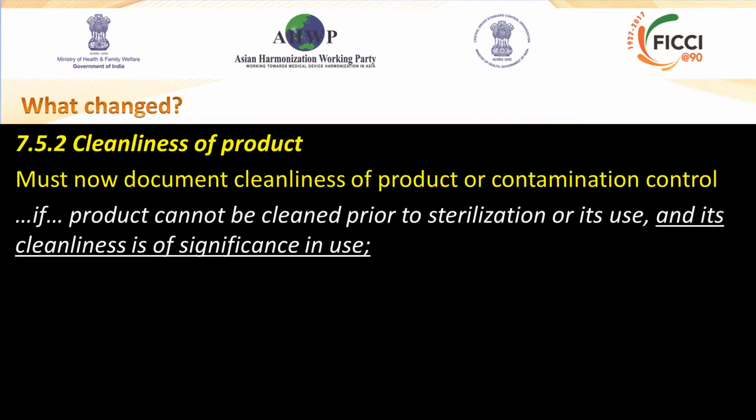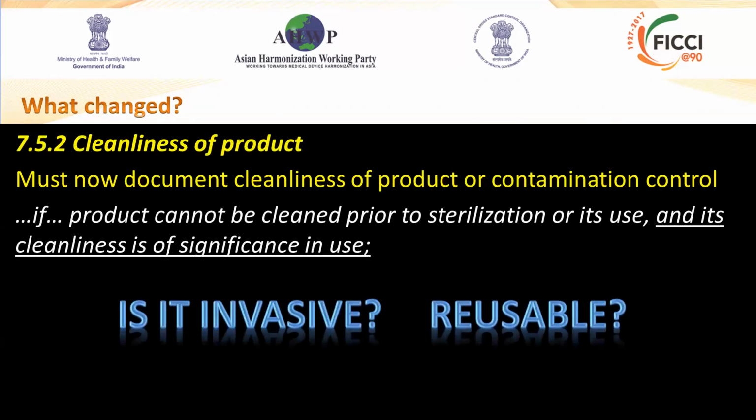There's also, again, more focus on cleanliness of products. It says if a product cannot be cleaned prior to sterilization or if its cleanliness is of significance in use, there has to be more control of the contamination. This is especially true of devices if it's invasive or reusable.